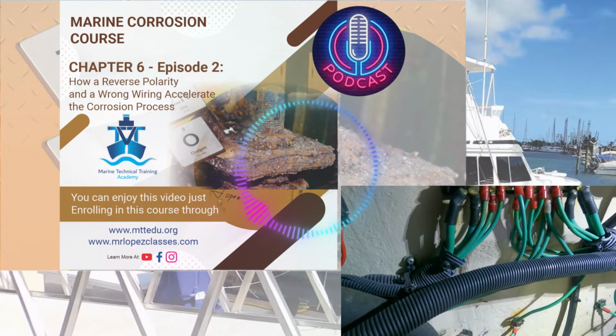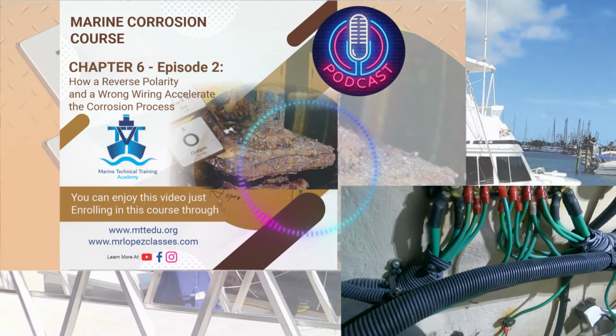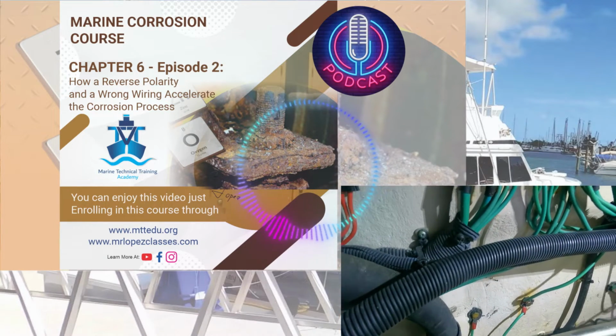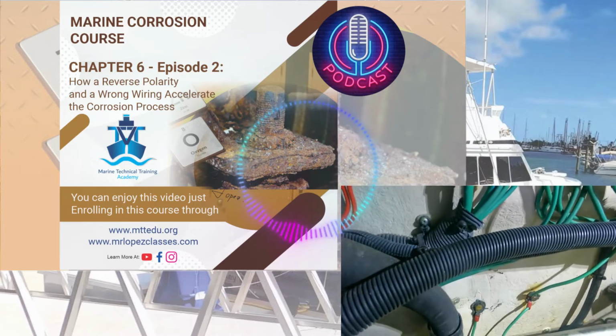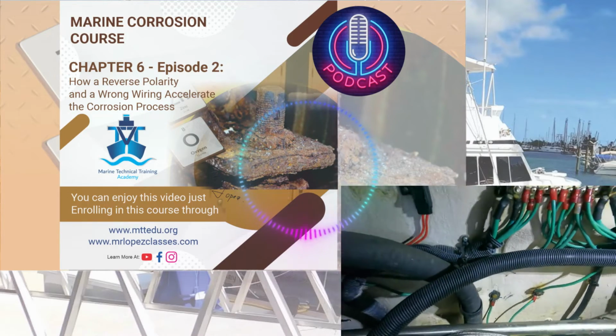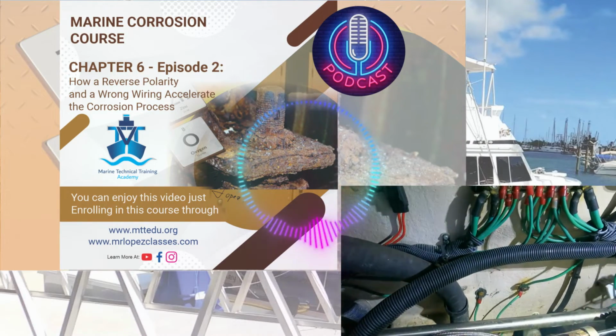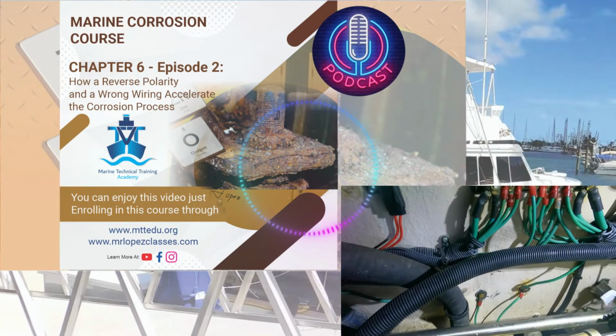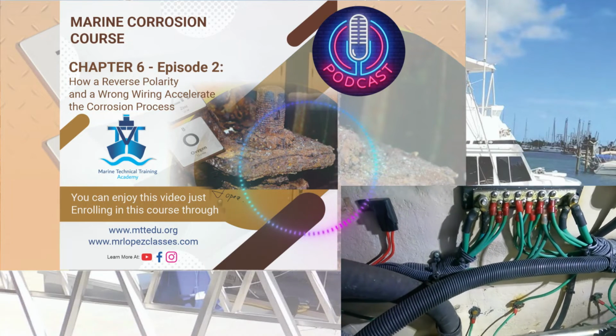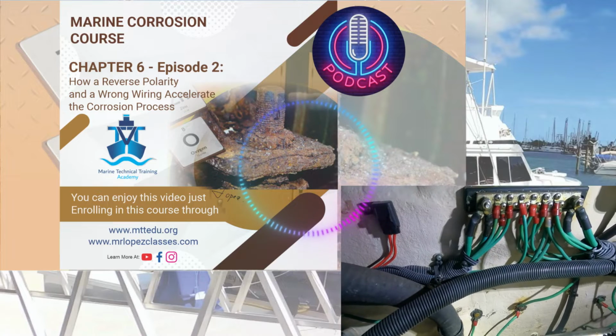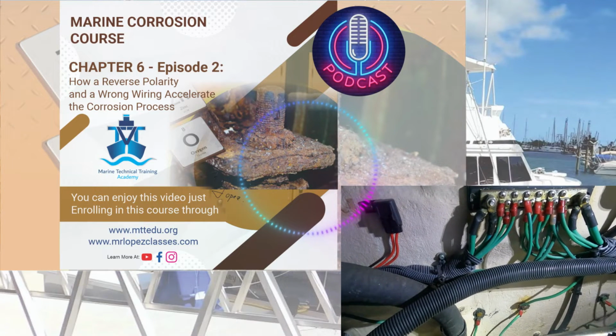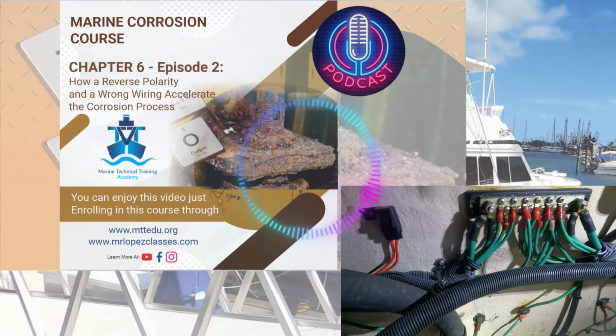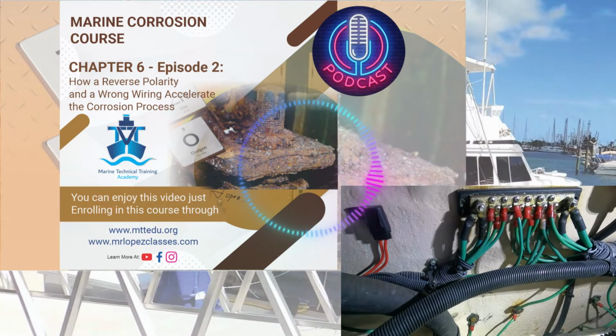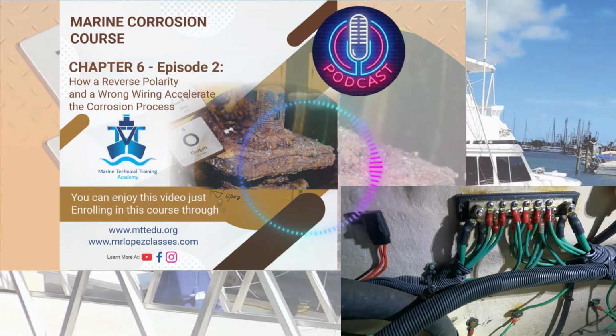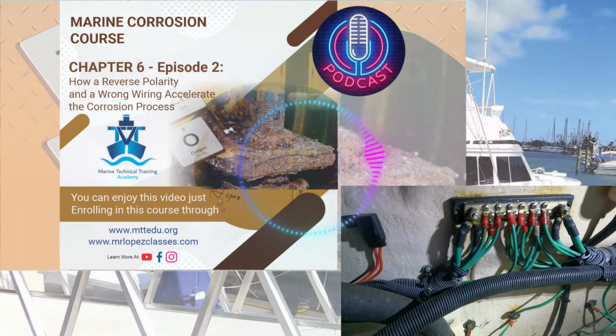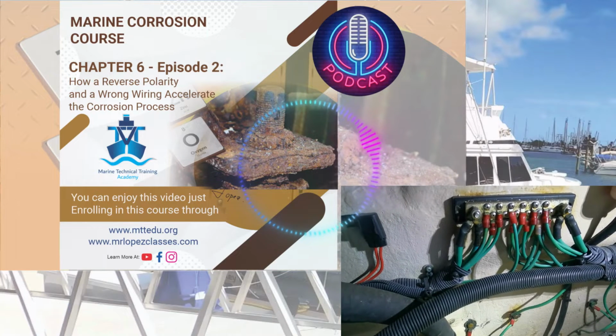Because if you have one of those, the neutral, with power, and suddenly some electrician, not a marine electrician, puts together the neutral and the ground bus bar, kaboom. This is catastrophic for your boat. Why? It's simple. Suppose that you have reverse polarity. In this moment, you have power in this bus bar. You have power in the neutral.